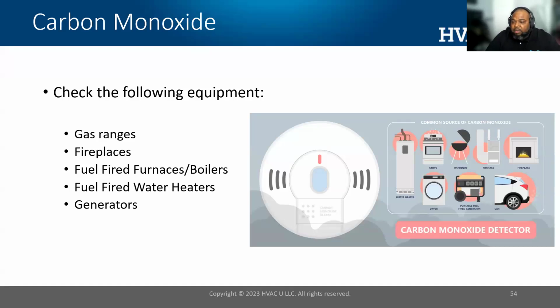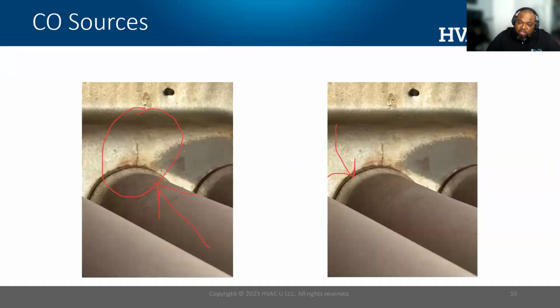You also want to check fireplaces. You want to check your fuel fired equipment, your furnaces, your boilers, your water heaters, and generators. Those need to be used appropriately as well. Now, even in the air conditioning season, it's important to test. This is right here, an image of a cracked heat exchanger, and if you're not familiar, this is the inside or internal parts of a furnace.